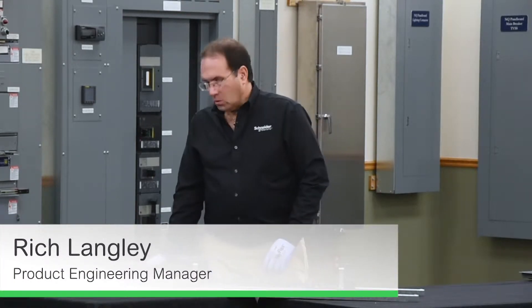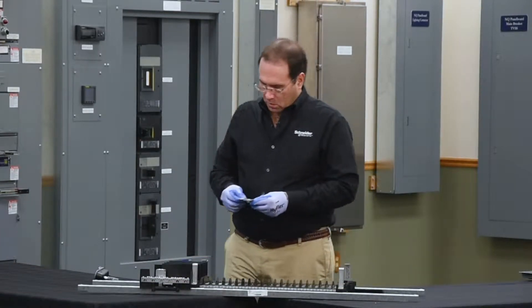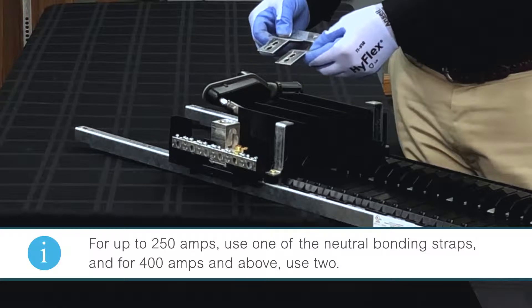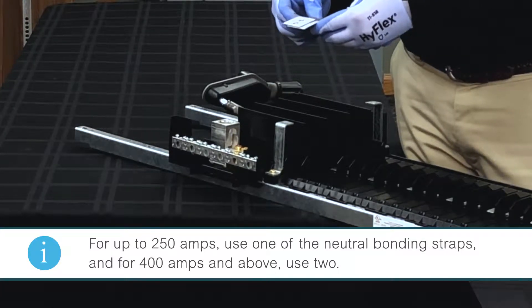In this video we'll be installing a neutral bonding strap on an NF panel board. The neutral bonding straps come in the bag included with the NF panel boards. For up to 250 amps you only use one, and for 400 amps and above you'll use two.